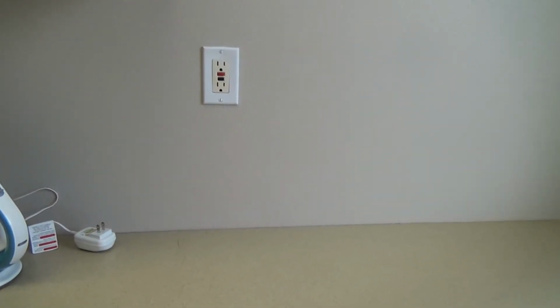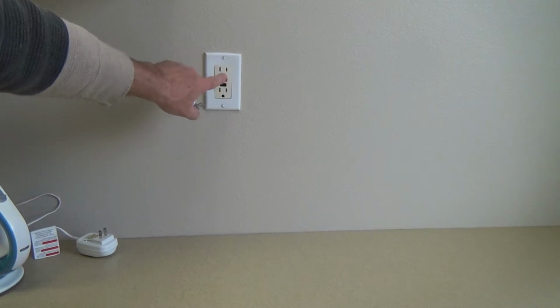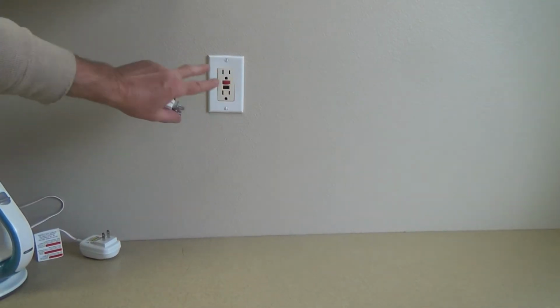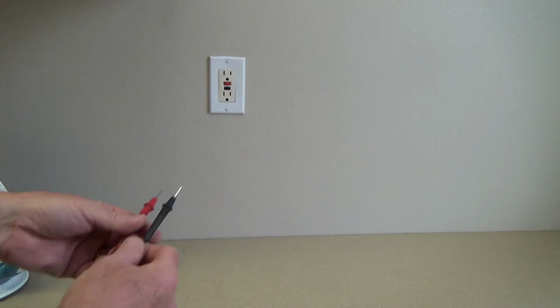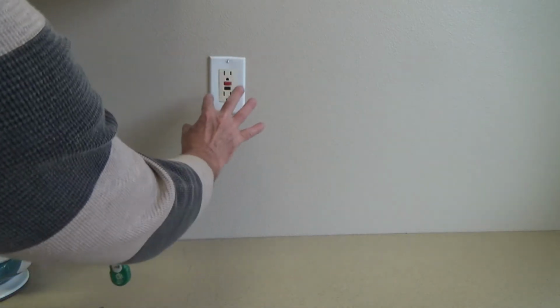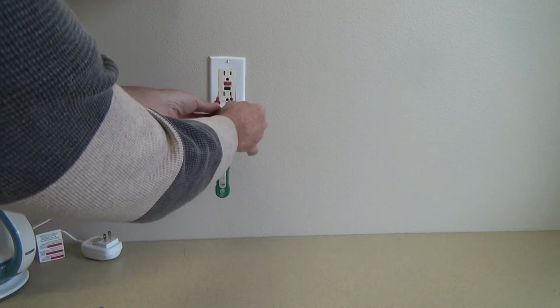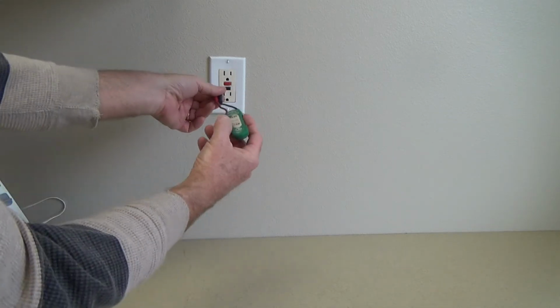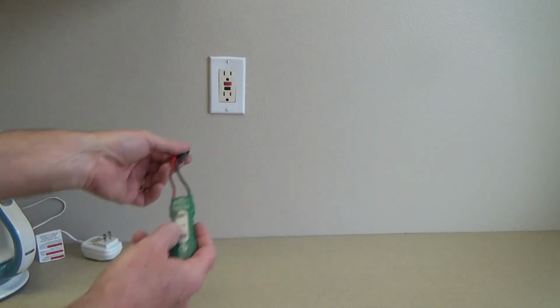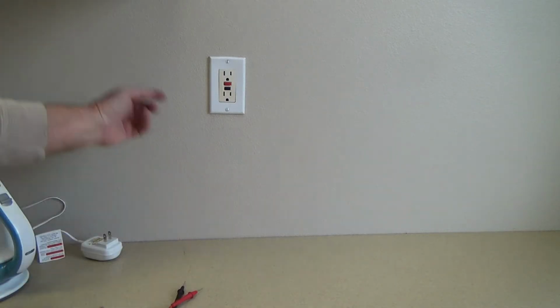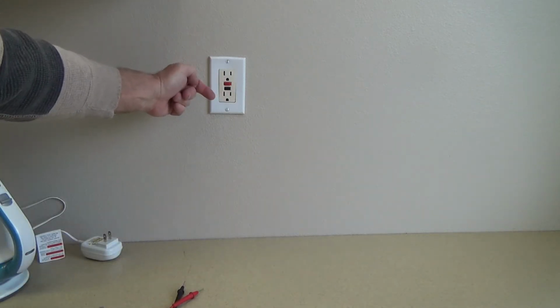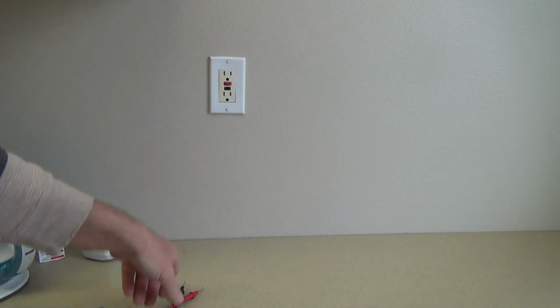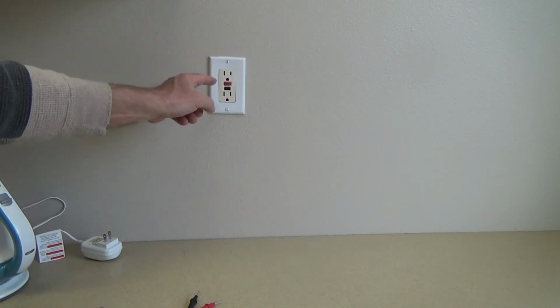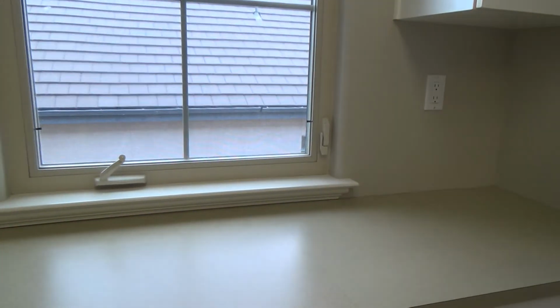If you didn't know that, and this was just an electrical outlet, you pull that out and you'd have the wire sticking out. You turn the breaker back on, isolate your wires in there, and check: one black and one white wire is going to be hot, the other black and white wire is not going to be hot. Only the ones coming into here would be hot, the other one's going out. Once you have it disconnected, you know those other wires go somewhere else, so let's say those other wires go over to there.